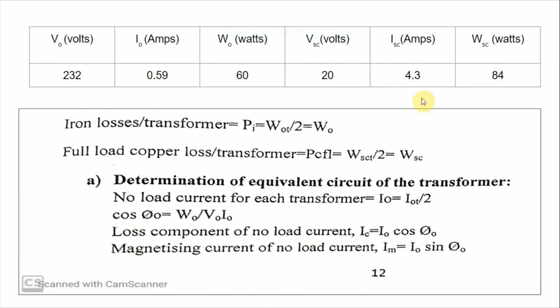These are the results we have obtained. These three readings are the OC readings, and these three are the short circuit readings. Now this calculation is similar to the OC/SC test calculation, with no much difference. Only the iron losses and full load copper loss we have read from the wattmeters are for two transformers, so for each transformer we need to calculate the iron loss and full load copper loss.